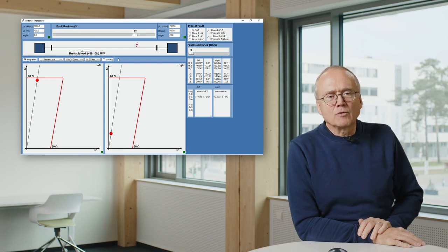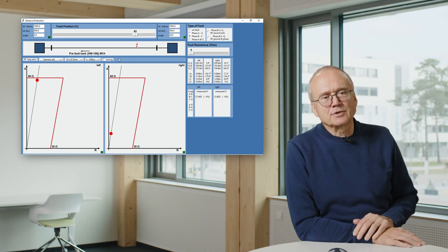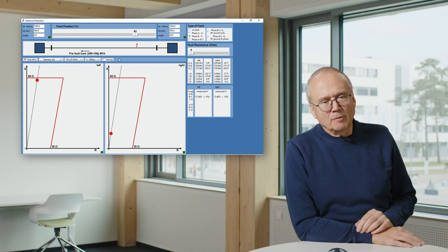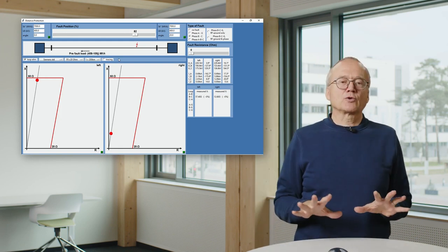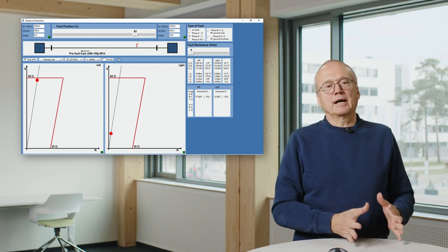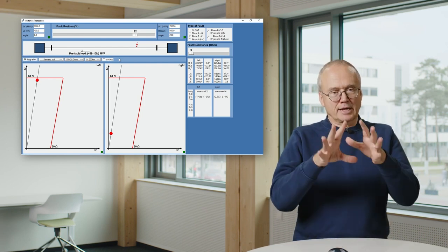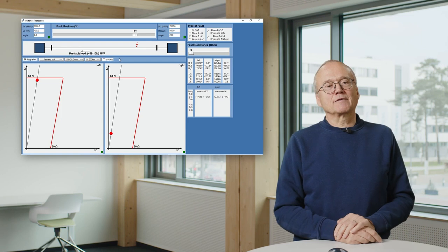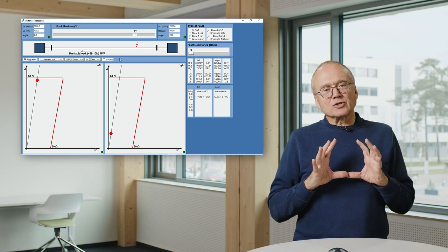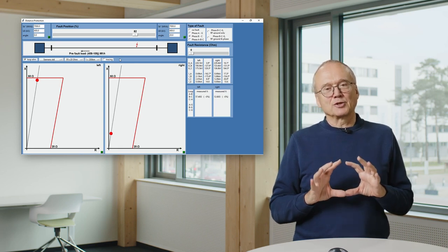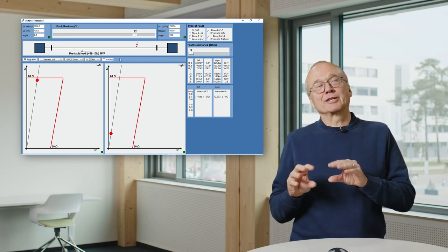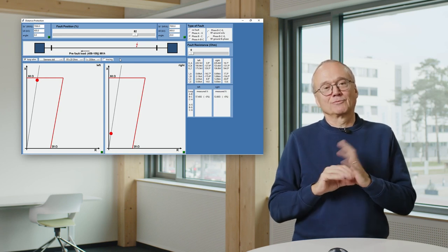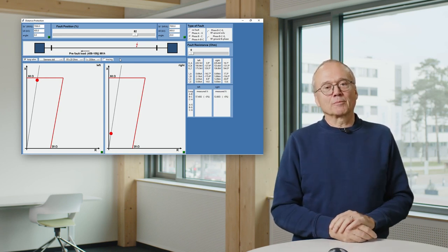And one thing we implemented and we really recommend is the so-called RMD method, or reactance method, in our protection relays. That means in our protection relays you have the possibility to activate either the conventional algorithms, as I showed up to now, or you can activate the RMD method, which then solves to a certain extent this problem. Unfortunately, you have to set again a few parameters.